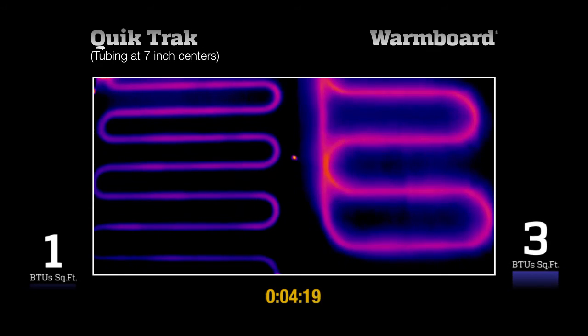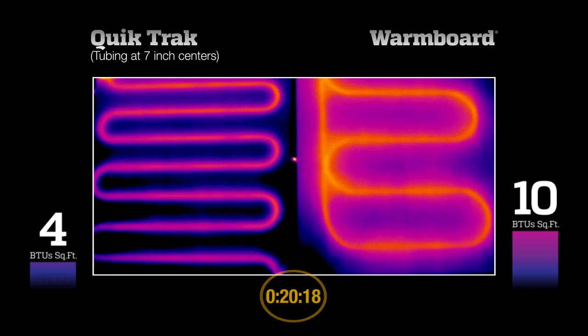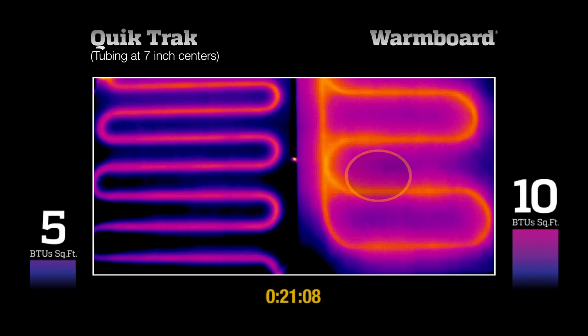10 BTUs per square foot is a common heating requirement on an average day in winter. WarmBoard reaches that requirement in about 20 minutes, and heat has flowed evenly across the panel. The Quik Trak system, with nearly twice the amount of tubing, is producing only 5 BTUs, with some areas of the surface not yet producing any heat at all.